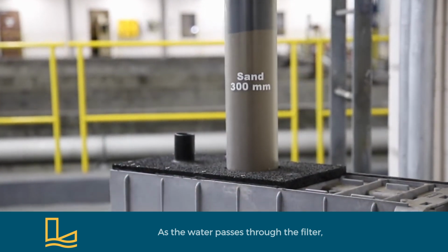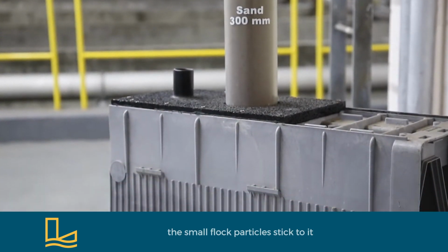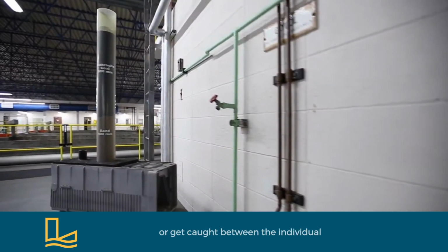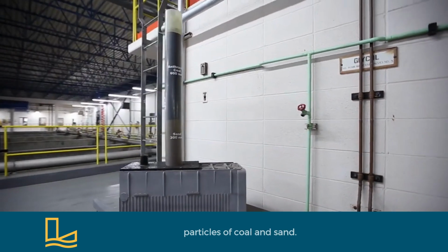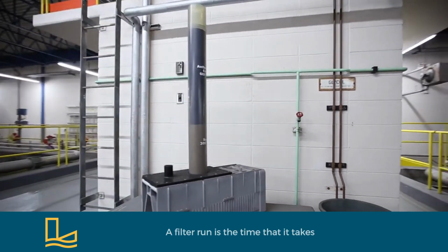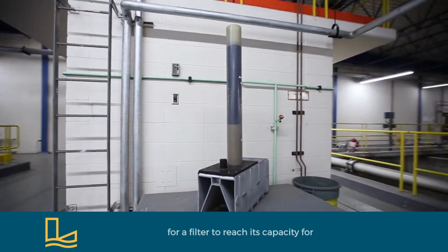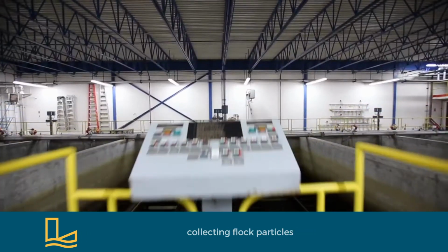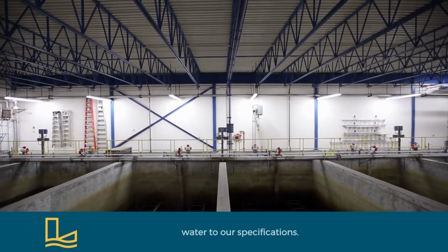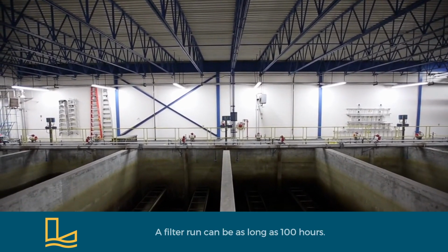As the water passes through the filter, the small floc particles stick to it or get caught between the individual particles of coal and sand. A filter run is the time that it takes for a filter to reach its capacity for collecting floc particles and no longer produces water to our specifications. A filter run can be as long as 100 hours.